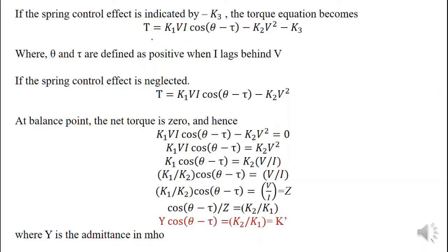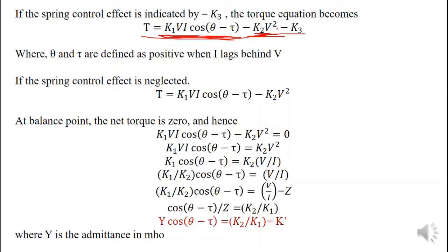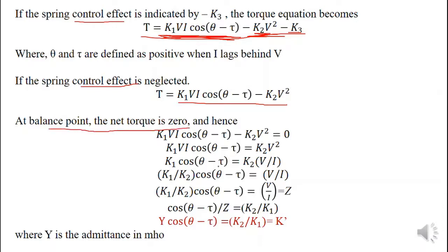The torque equation of the Mho relay is as follows: K1VI cos(θ − τ) represents the operating torque produced by the voltage-current directional element; K2V² is the restraining torque produced by the voltage element; and K3 is the spring control effect. Neglecting the spring control effect, K3 equals zero. Considering the normal operating condition at the balance point, the torque equation equals zero. Modifying this equation, we finally obtain Y — the admittance — equal to a constant K. This is the torque equation representation of the Mho relay.